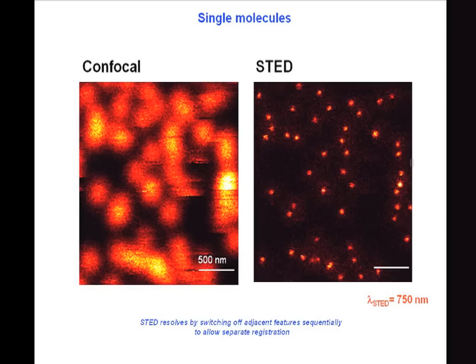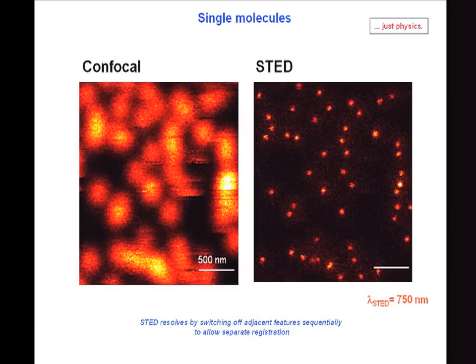This is shown in this comparison. On the left-hand side you see a confocal recording of individual molecules dispersed on a surface, and now you see the STED counterpart. One is able to discern molecules that are very close to each other, because they emit at different points in time — whereas in a confocal microscope you cannot discern them because they give off light basically at once. The point is that we just use molecular transitions of the dye — this is a physical phenomenon — there is no need for any computation or image restoration. This is the strength of the method.